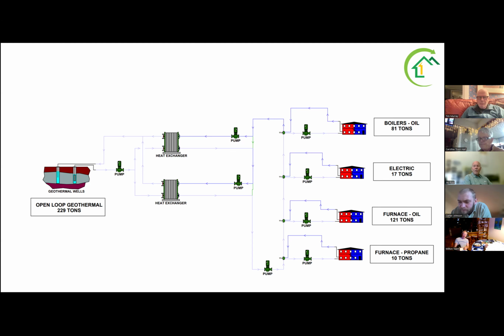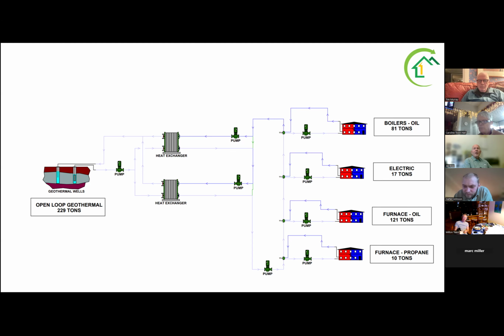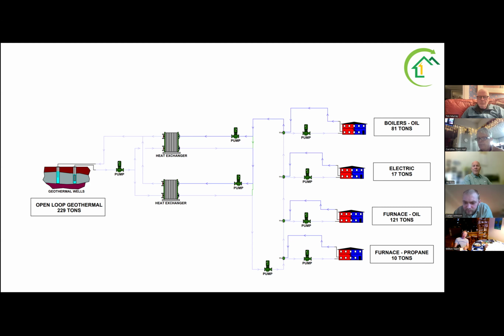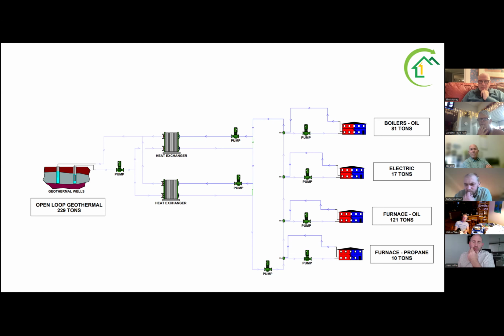I don't know if Carter knows that off the top of his head, but if you're doing forced air, the supply temperature coming out of the grill is normally about 30 degrees above target. So if you're looking for 75-degree comfort, the temperature across the coil will be 30 degrees warmer, meaning your air coming out of the vent will be north of 100 degrees. As far as hydronic systems, if you've got an in-floor heating system or radiators, that temperature will come out as warm as 145 degrees.